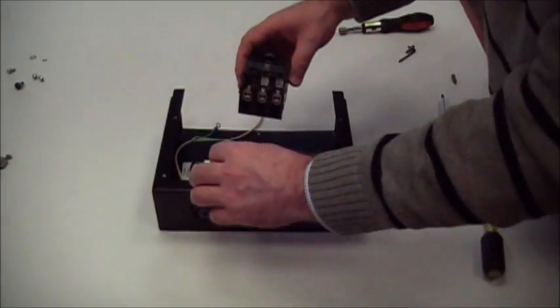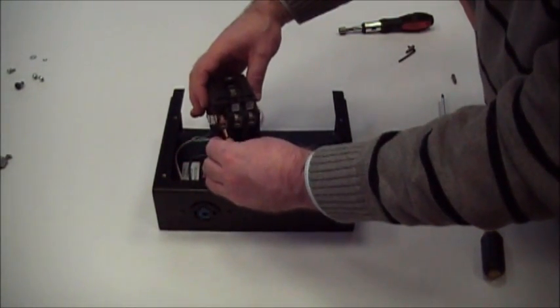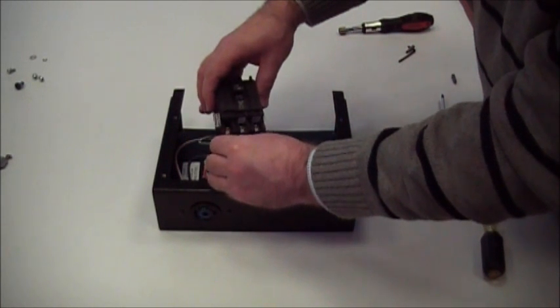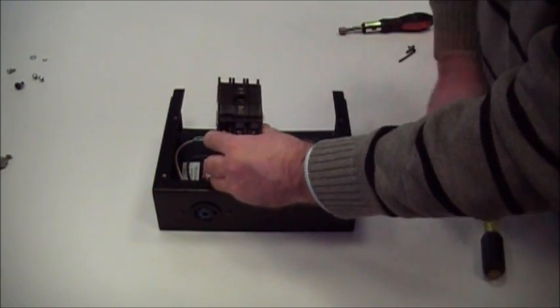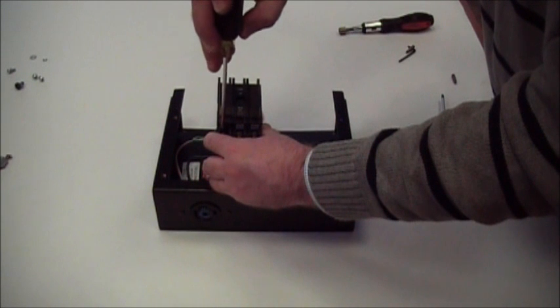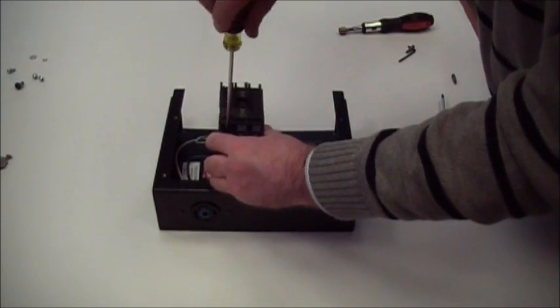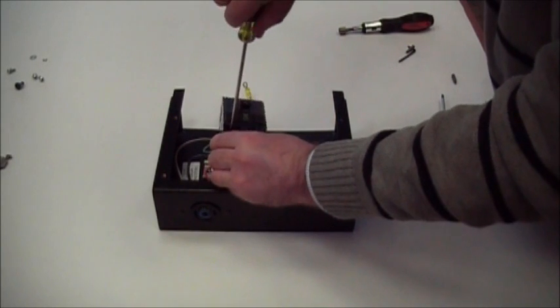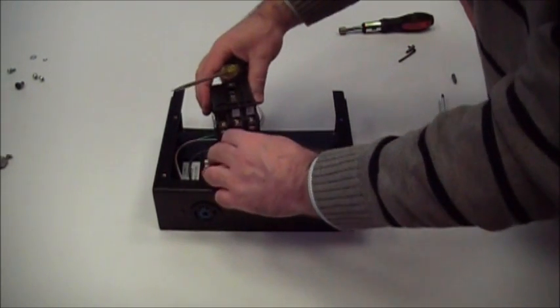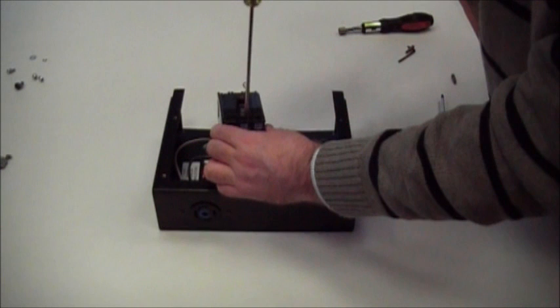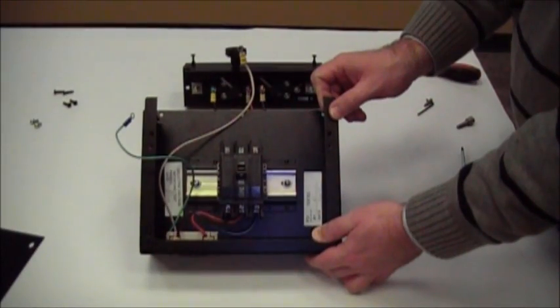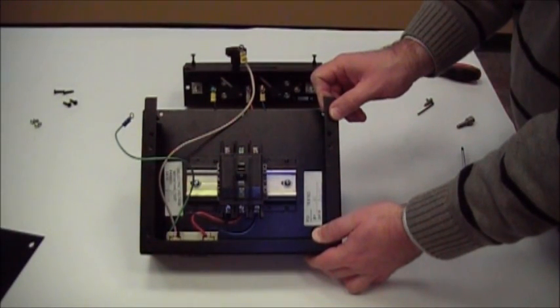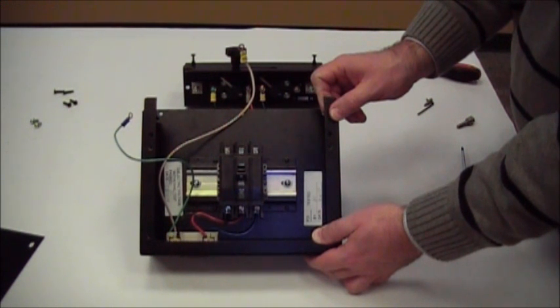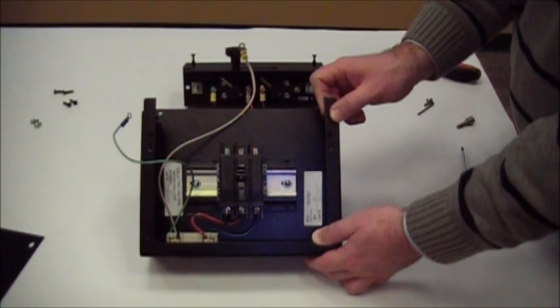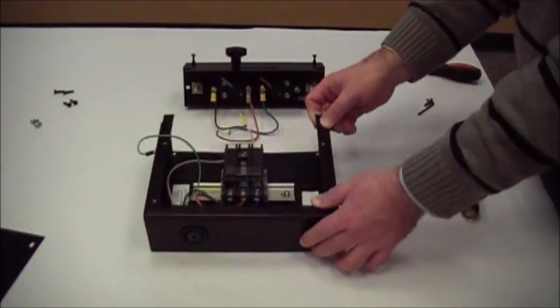Next we'll take the enclosure, and you can see the receptacles already mounted in the enclosure, and what we'll do is wire the load side of the breaker to the receptacle and then install that in the enclosure, and then we will assemble the paddle and mechanism. Okay, so we have the box together somewhat with the breaker and receptacle wired on the load side. Now we'll put the paddle assembly and wire in the top side of the breaker.